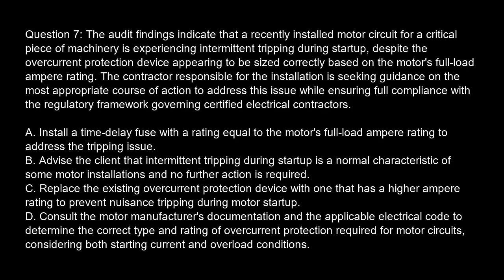Option A. Install a time delay fuse with a rating equal to the motor's full load ampere rating to address the tripping issue. Option B. Advise the client that intermittent tripping during startup is a normal characteristic of some motor installations and no further action is required. Option C. Replace the existing overcurrent protection device with one that has a higher ampere rating to prevent nuisance tripping during motor startup. Option D. Consult the motor manufacturer's documentation and the applicable electrical code to determine the correct type and rating of overcurrent protection required for motor circuits, considering both starting current and overload conditions.